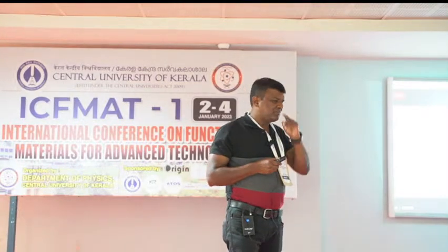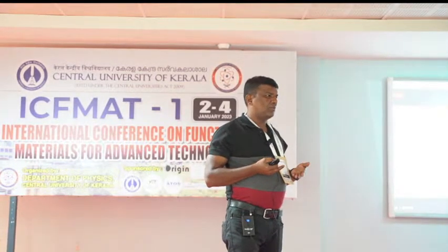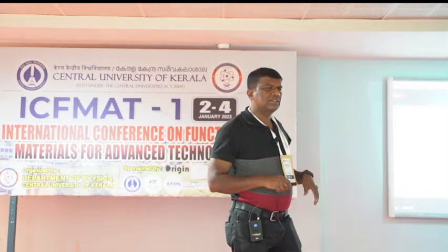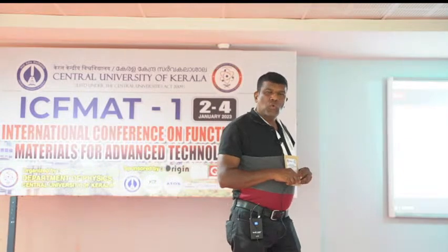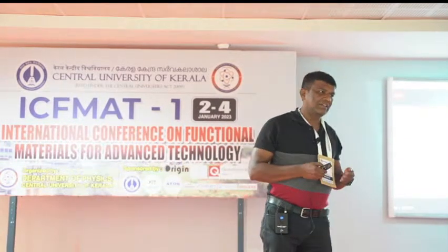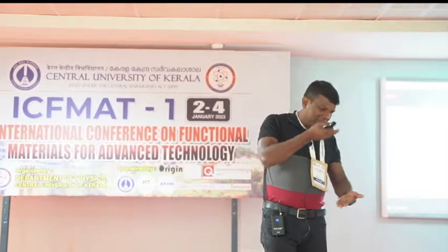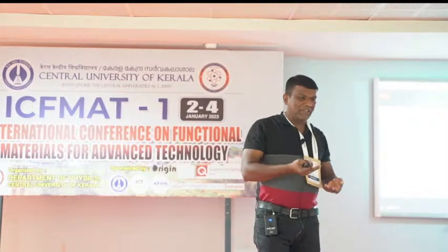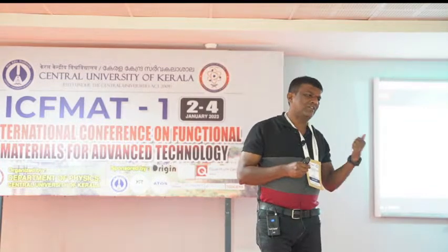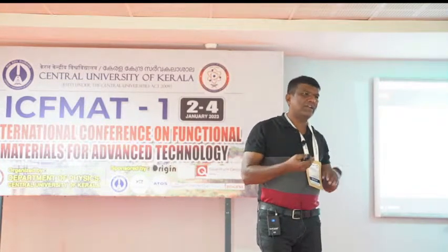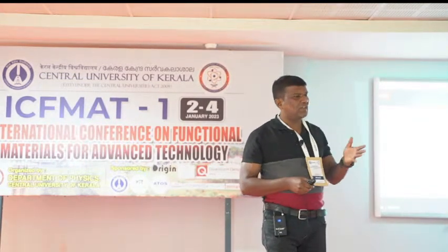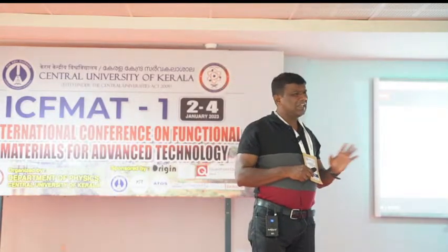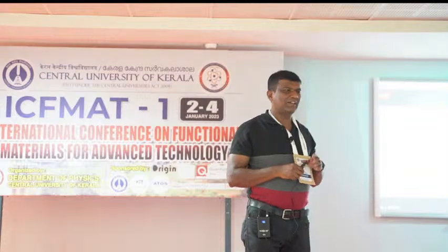Also, the optical microscope condenser should have a working distance of around 73 millimeters or higher. If the working distance is lower than that, there will be no room to put the scan head in between. That is the requirement: the objective, the adapter and the condenser should have a working distance of around 73 millimeters or higher. Except for that, any optical microscope available on the market is fine.